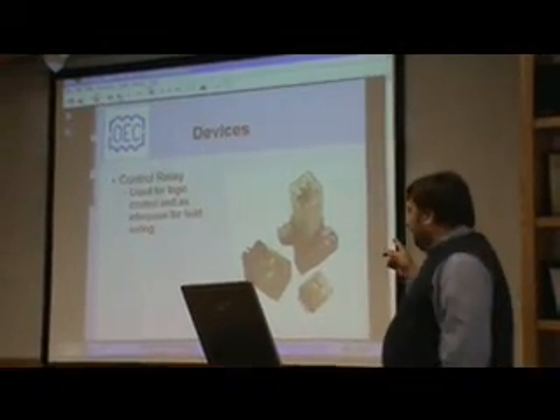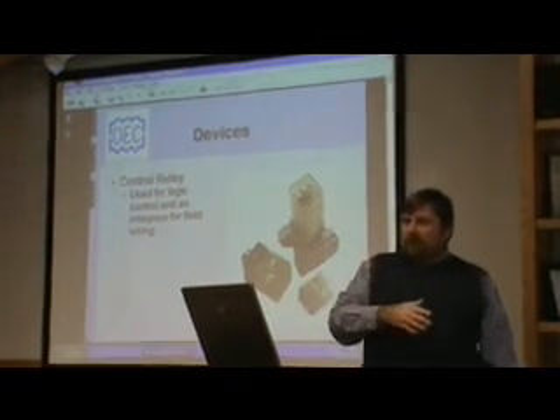And there again, they're going to be rated at the 120 volts for your control. But the contacts on these larger relays, you can get a 10 amp rating through the contact. So if you need to run some type of a circuit through there, it will take up to 10 amps.